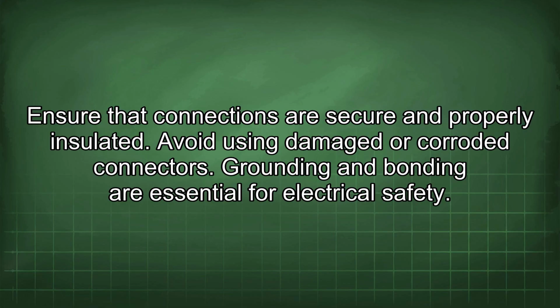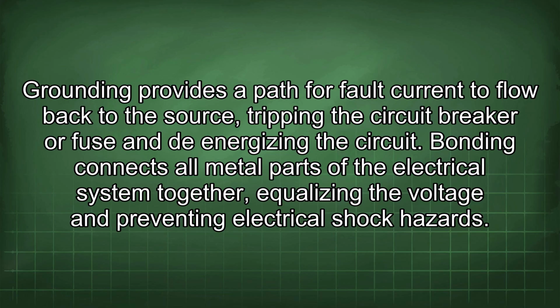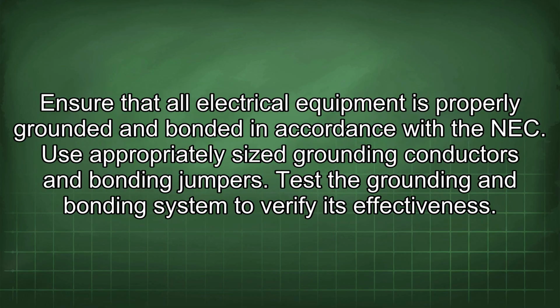Grounding and bonding are essential for electrical safety. Grounding provides a path for fault current to flow back to the source, tripping the circuit breaker or fuse and de-energizing the circuit. Bonding connects all metal parts of the electrical system together, equalizing the voltage and preventing electrical shock hazards. Ensure that all electrical equipment is properly grounded and bonded in accordance with the NEC. Use appropriately sized grounding conductors and bonding jumpers.